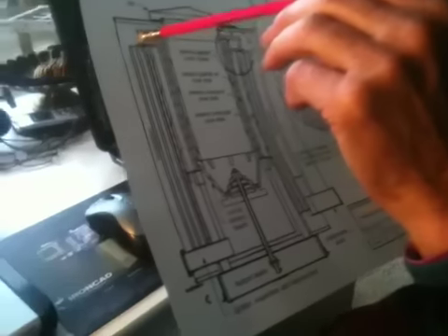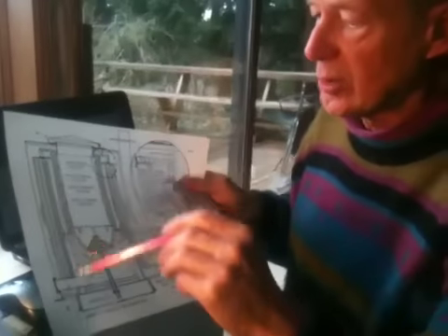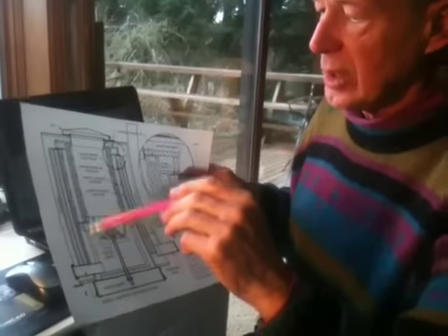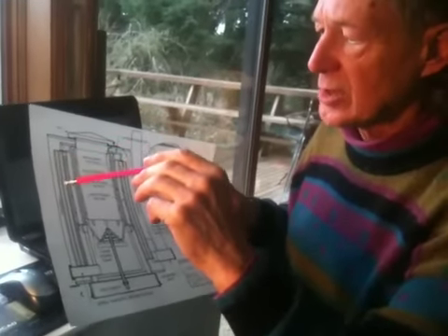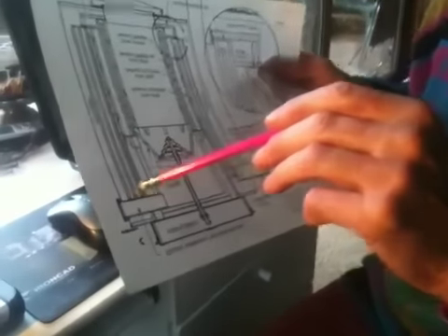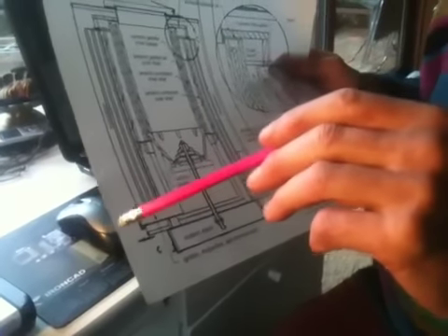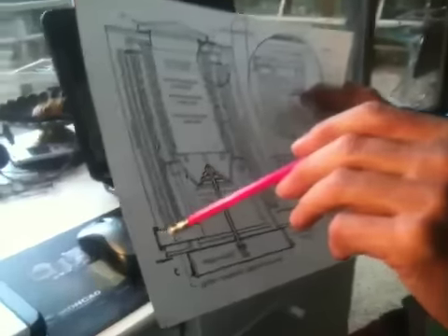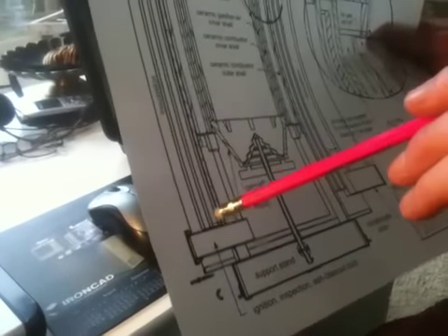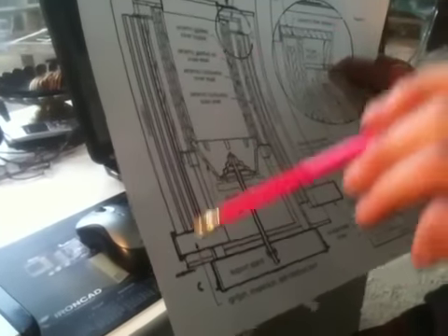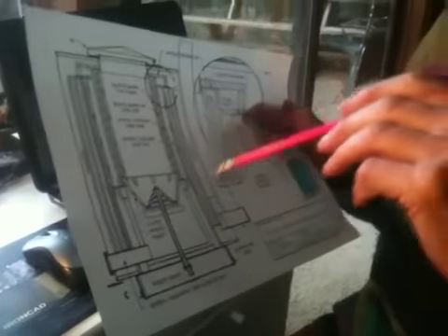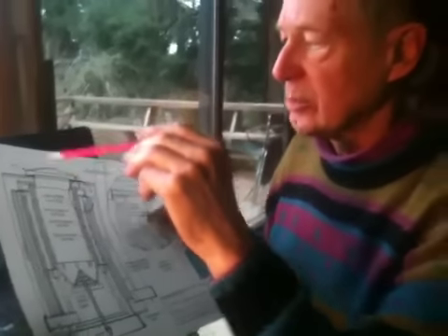As the gas goes by the water heat exchanger shell, it heats the water as it cools and drops and ends up going out the bottom of the heat exchanger shell, while the water comes in cool at the bottom, and it goes in the spiral and comes out hot in the middle at the top.